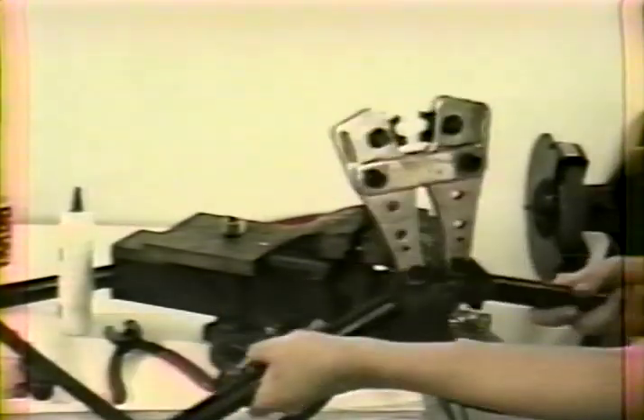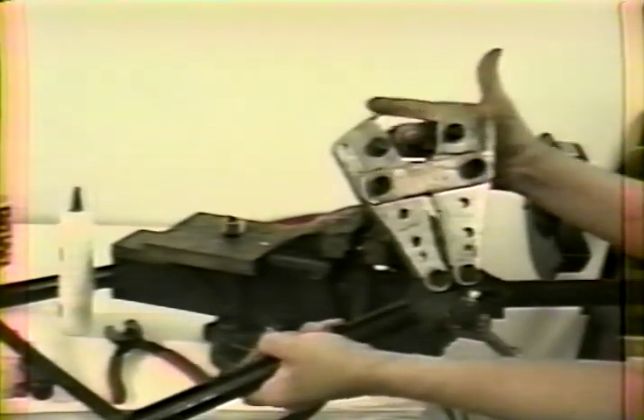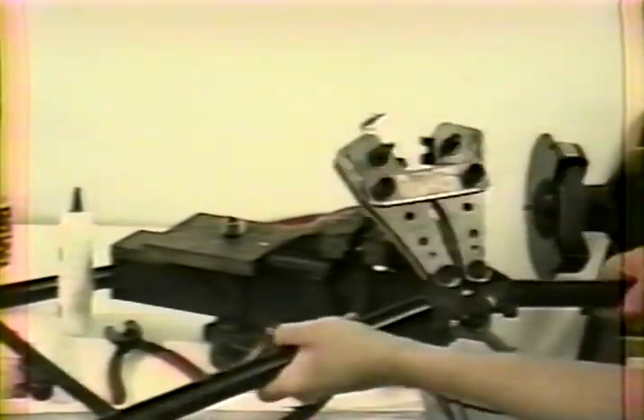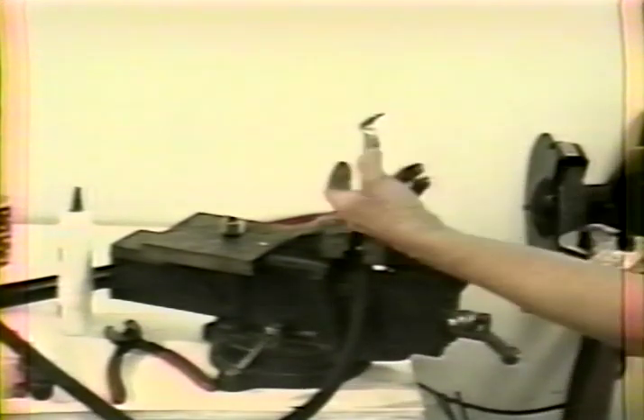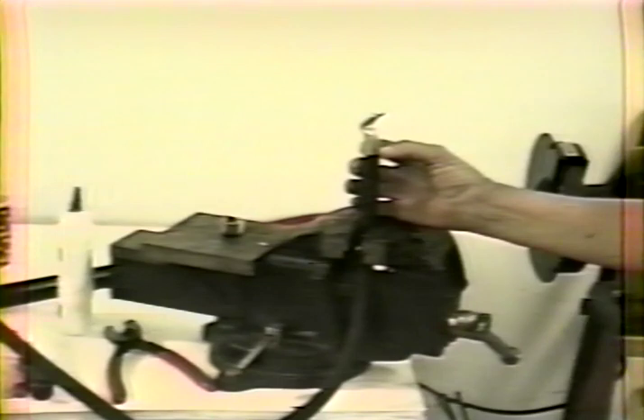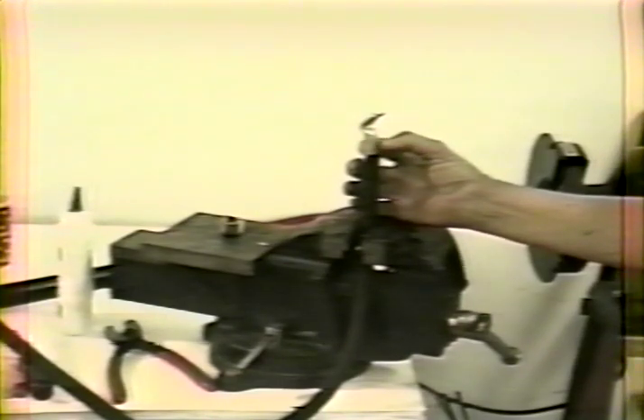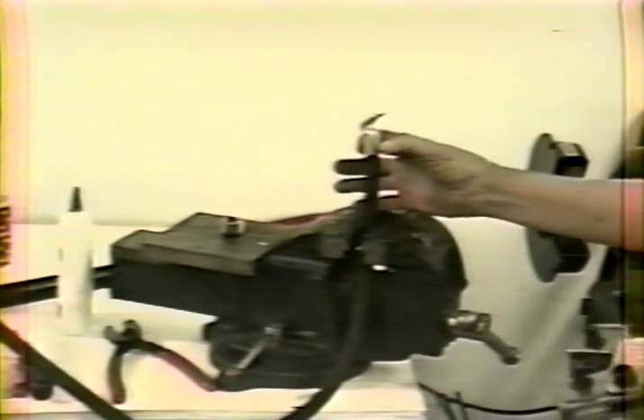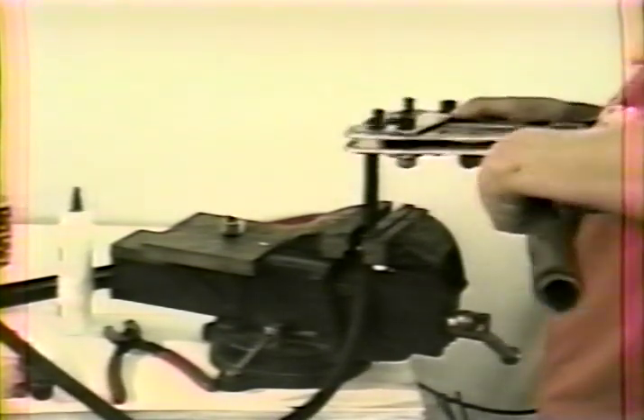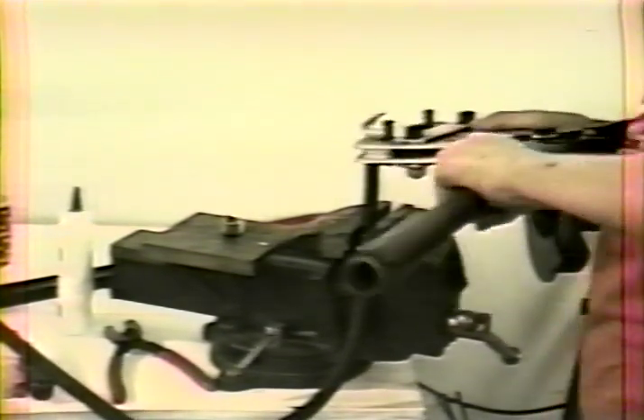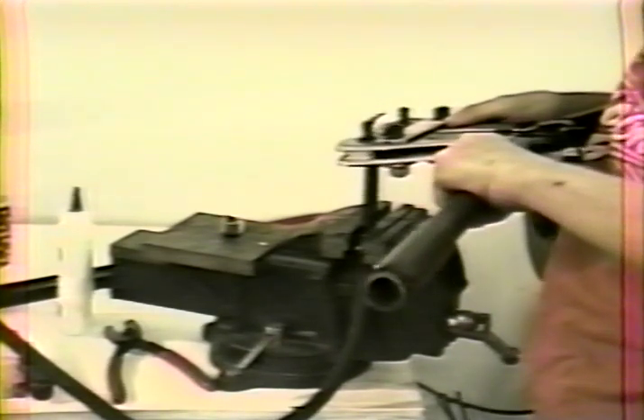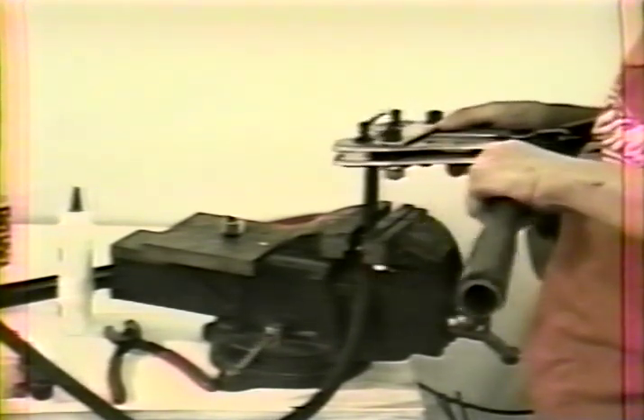You see, it's set to 2/0, the size we need, and you put it on, and you want to put 2 crimps. The second one will be right at the very bottom, and the first one will be up a little higher, so you do the higher one first. Some lugs actually have lines showing you where to put them. This particular one doesn't, but I know where to put it.